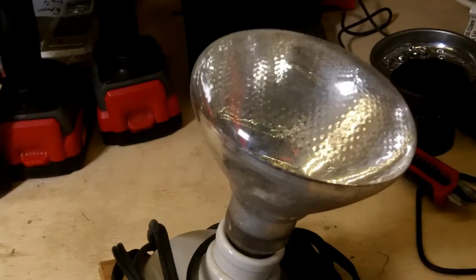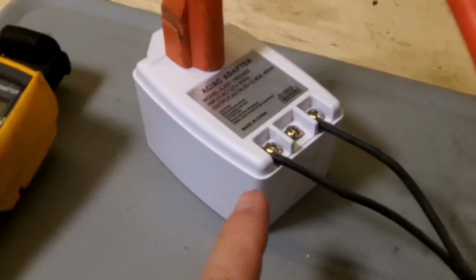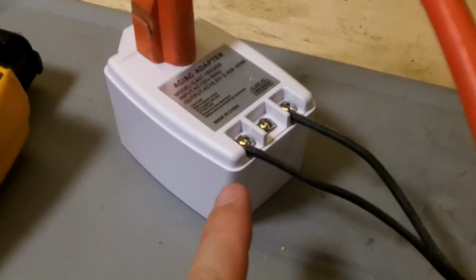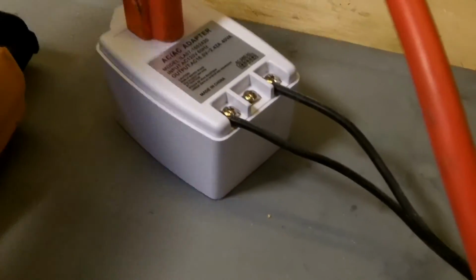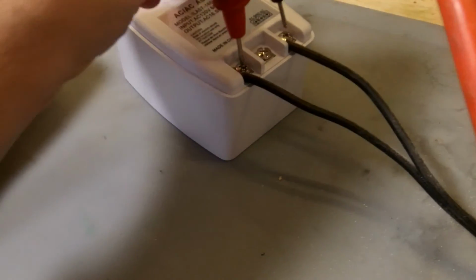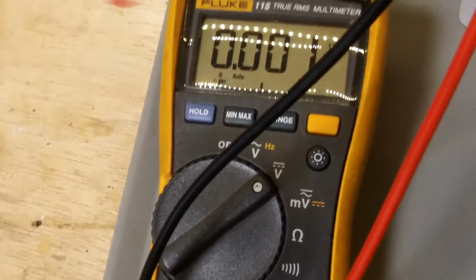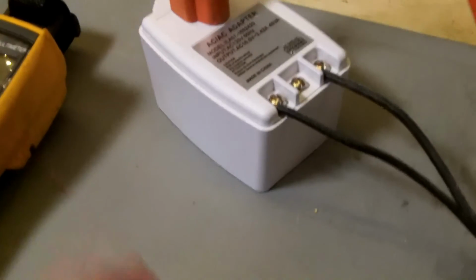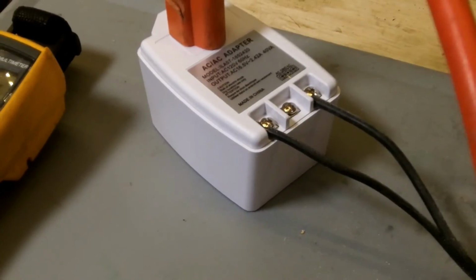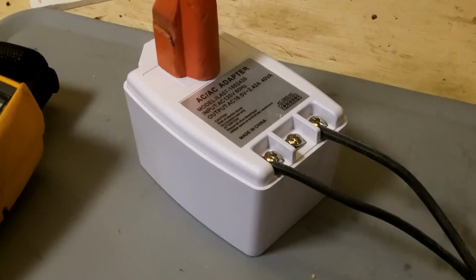So I've hooked this up to a resistive load, a 120 volt light bulb. I don't know if you can see it, but the filament is glowing slightly. Obviously it's not able to provide enough voltage for this bulb to fully light, but it's drawing as much current as it can. The voltage sags down to almost 0 volts, because it's driving essentially a short circuit. But it's still delivering power to that filament, so it's working fine driving a short circuit.